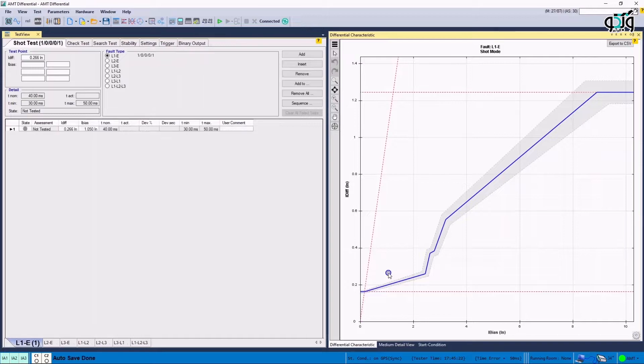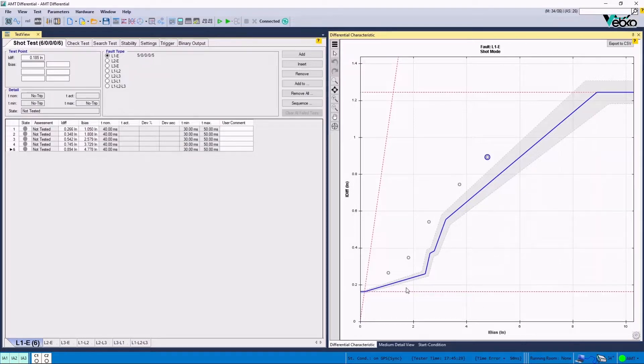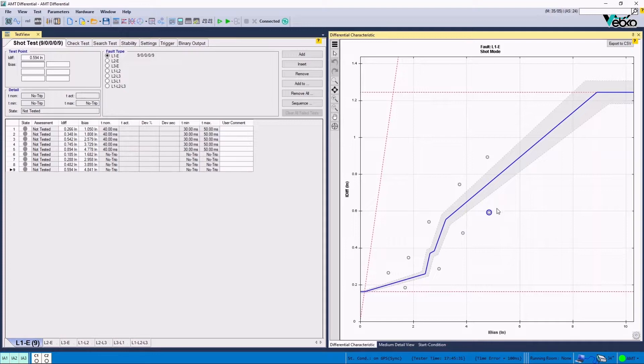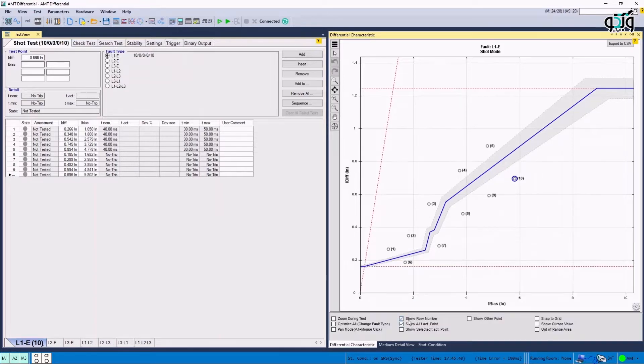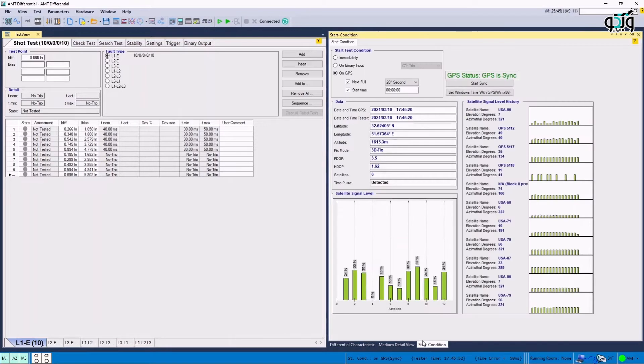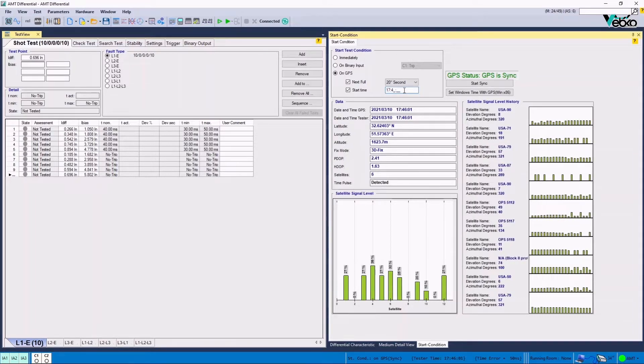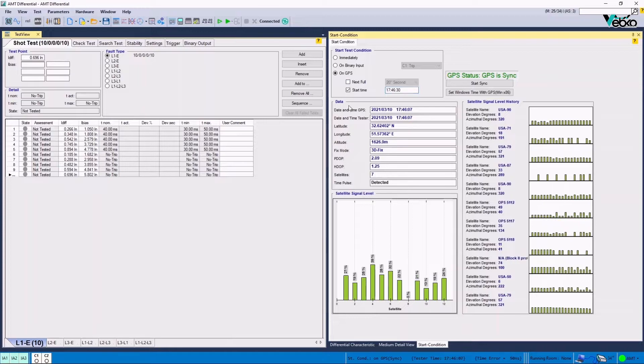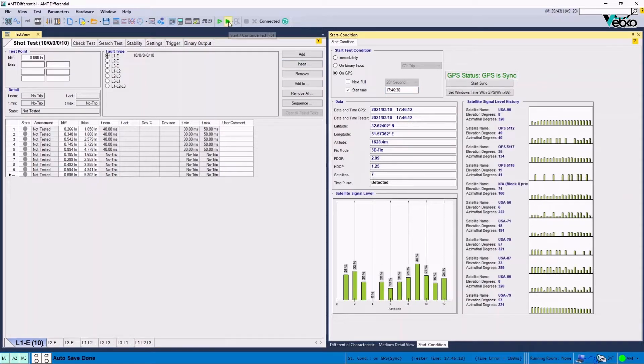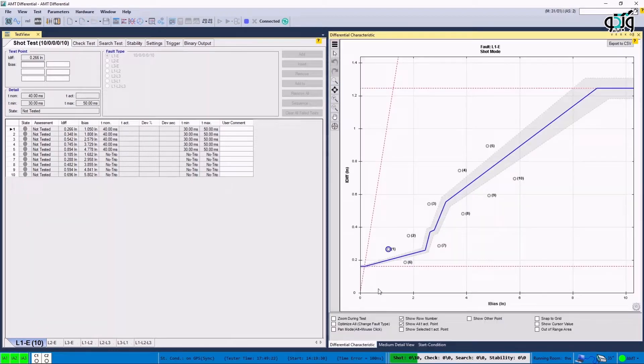In the next step, after coordinating with the opposite side, some points are put on the differential characteristic and after adding them to the test table, it is possible to compare their coordination which is a combination of I bias and I diff to ensure that the conditions are the same. By clicking on the cog icon at the bottom of the differential characteristic window, it is possible to use the features that help users to better supervise the test. Now, by returning to Start Condition tab in On GPS section, a time is considered as the start time after coordination with the opposite side. And then by unchecking NextFull option, whose function has been explained before, the test begins.